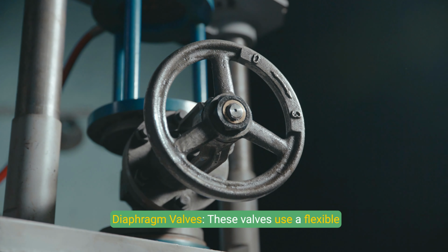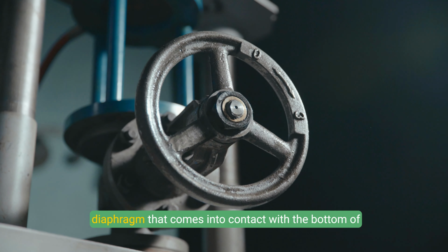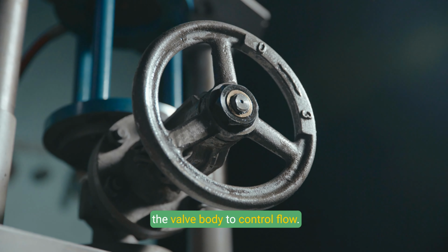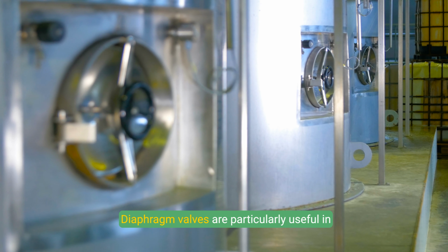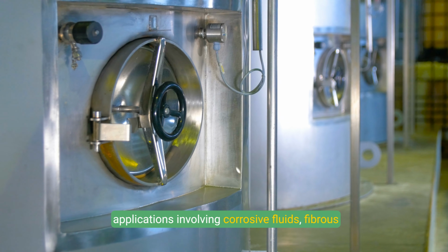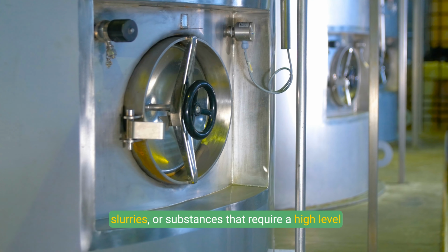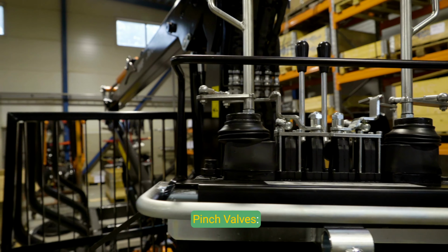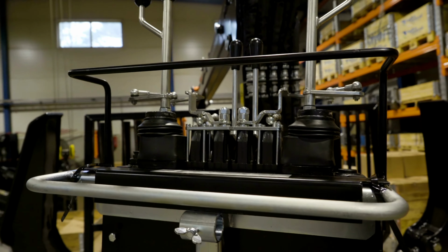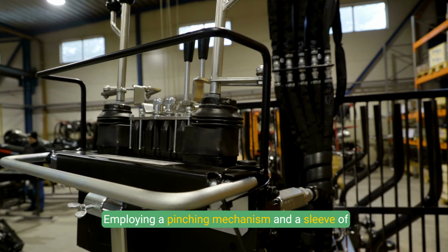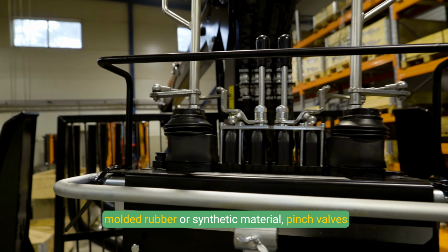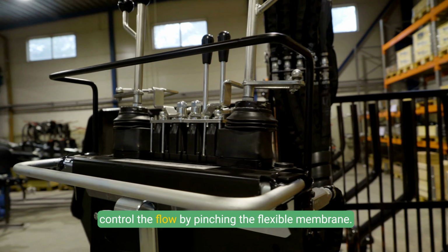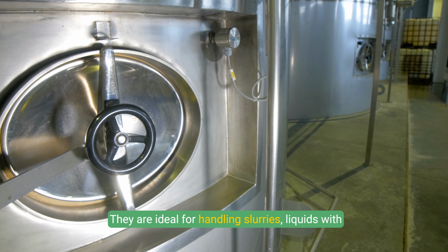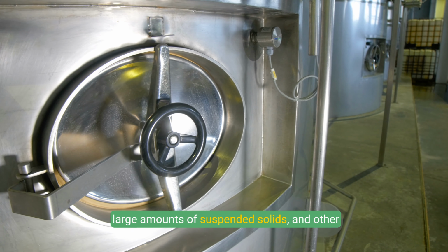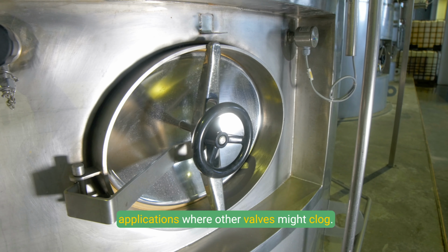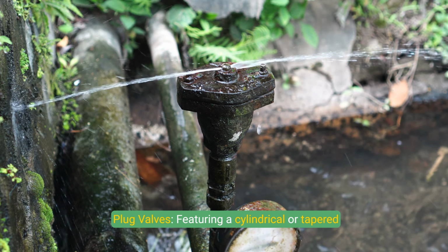Diaphragm valves. These valves use a flexible diaphragm that comes into contact with the bottom of the valve body to control flow. Diaphragm valves are particularly useful in applications involving corrosive fluids, fibrous slurries, or substances that require a high level of purity. Pinch valves. Employing a pinching mechanism and a sleeve of molded rubber or synthetic material, pinch valves control the flow by pinching the flexible membrane. They are ideal for handling slurries, liquids with large amounts of suspended solids, and other applications where other valves might clog.